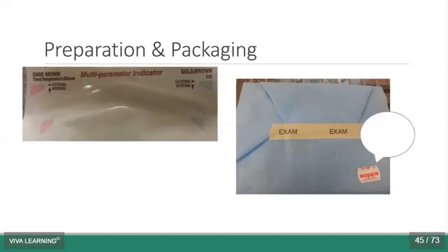The other thing about preparation and packaging that I see a common observation is that we're not labeling our packages, right? And we want to make sure that when we're labeling our packages, at a minimum, we want to put the date that it was sterilized, as well as which sterilizer we used. So we have multiple sterilizers. We're going to number them A, B, or C, or 1, 2, or 3, whatever the case may be, and then which cycle we are on for that day.